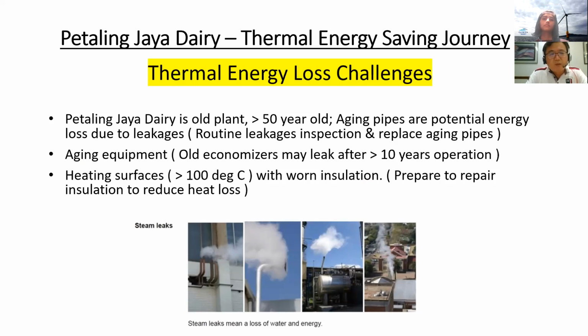Some of our old economizers we are also planning to replace, because they may leak after more than 10 years of operation. The third is heat surfaces at high temperature with worn insulation. We are trying to address this with the hotspots found using thermal imaging, so we are replacing the insulation. Okay, next slide, please.